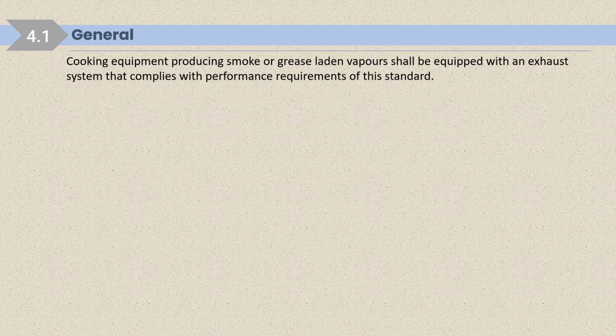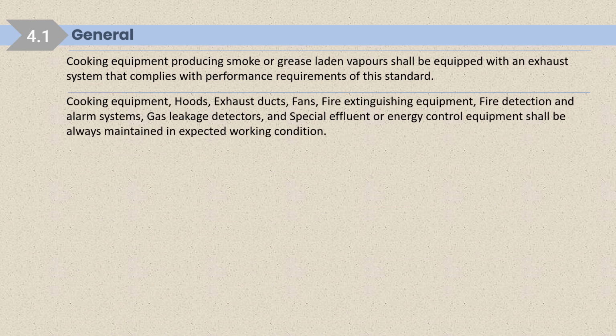In this 4.1, it is mentioned that cooking equipment producing smoke or grease-laden vapor shall be equipped with an exhaust system that complies with the performance requirements of this standard. We are going to see the performance requirements of the exhaust system in this standard. Cooking equipment, hoods, exhaust hood ducts, fans, fire extinguishing equipment, fire detection and alarm system, gas leakage detectors and special effluent or energy control equipment shall always be maintained in expected working condition. So whatever equipment is there to control the grease or grease-laden vapor has to be in working condition all the time.